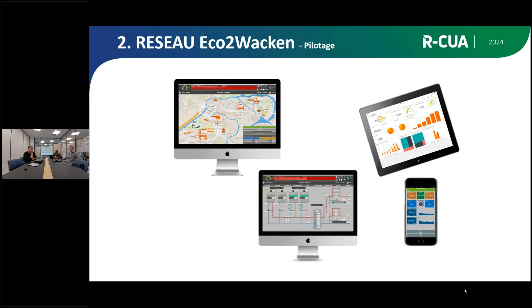Le pilotage est un enjeu majeur des réseaux de chaleur à l'heure actuelle. On n'est plus sur des fonctionnements d'installations comme il y a 10-20 ans. Toutes nos installations sont interconnectées entre sous-stations et centrales de production par de la fibre optique. On a accès à distance avec n'importe quel smartphone, tablette ou PC à l'ensemble des données en temps réel pour faire des analyses énergétiques, du pilotage en temps réel, des levées de doute sur différents défauts, et optimiser le fonctionnement. Ce sont des solutions développées en propre par nos automaticiens et informaticiens.